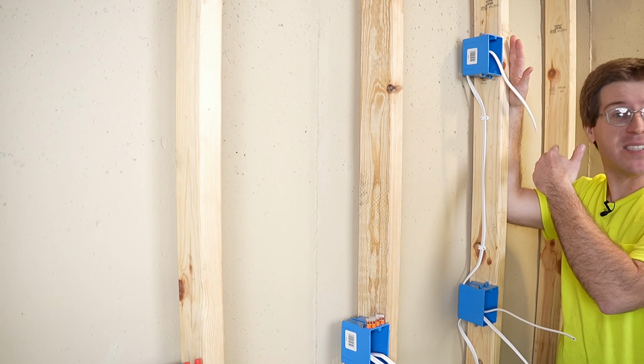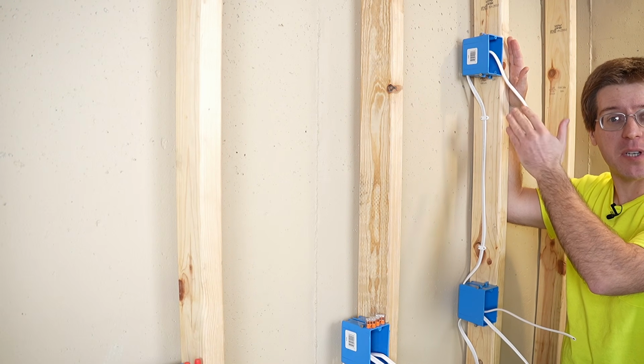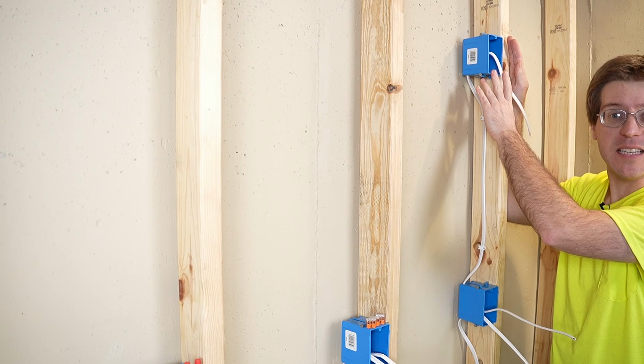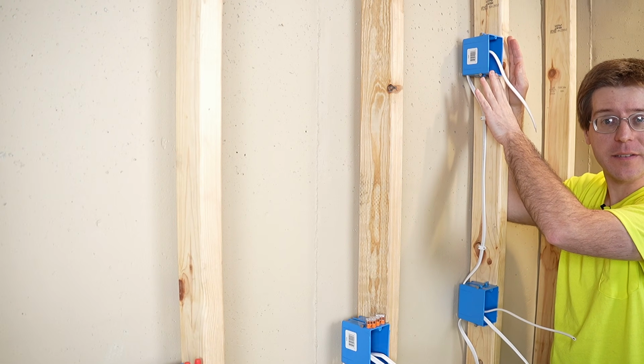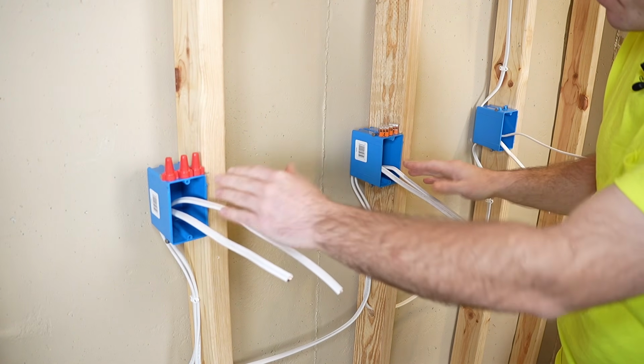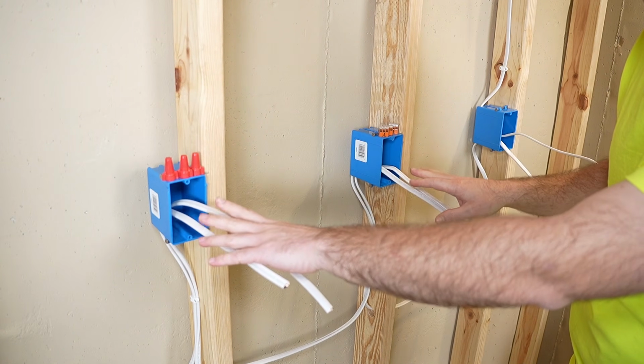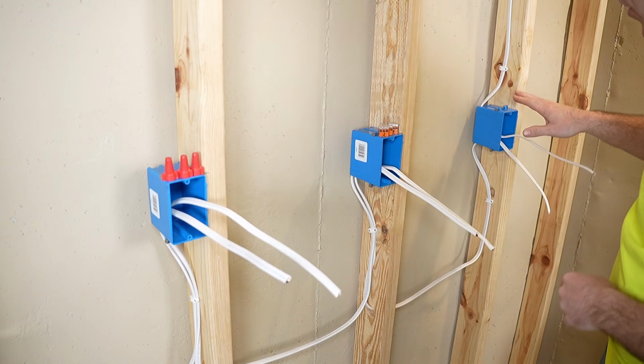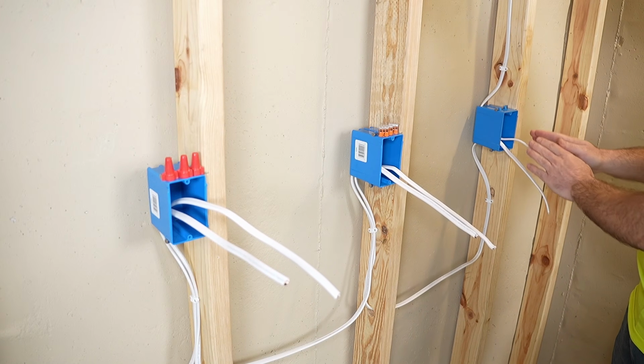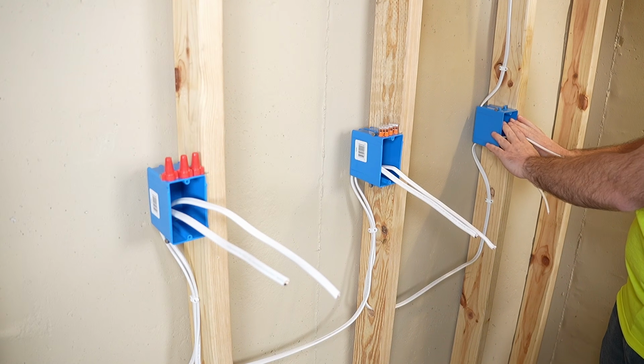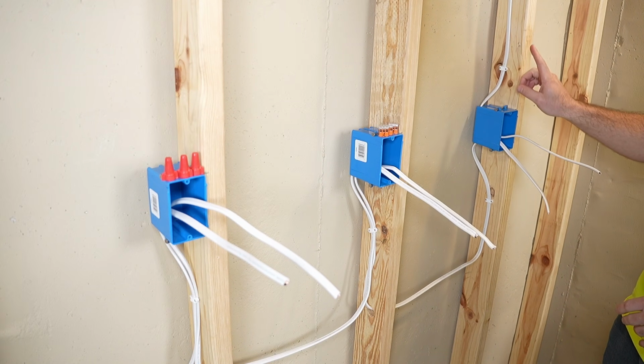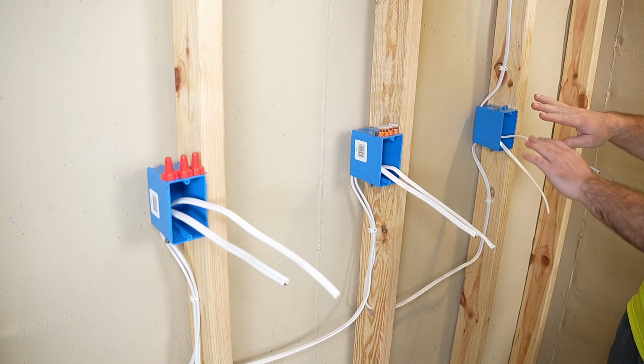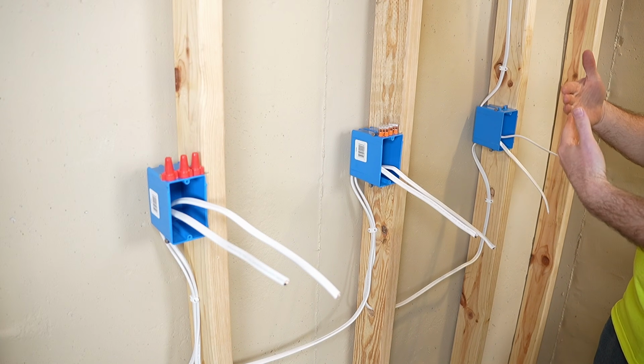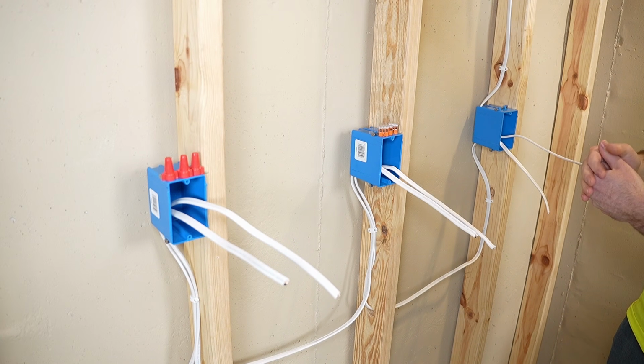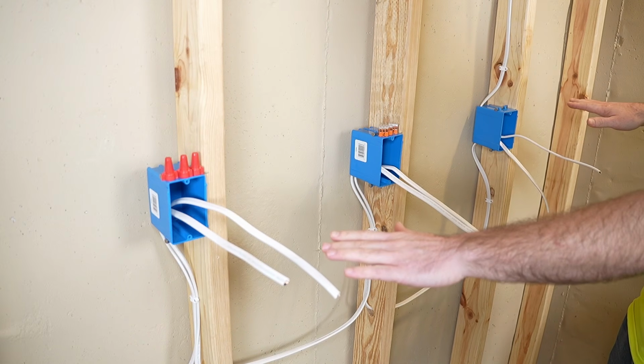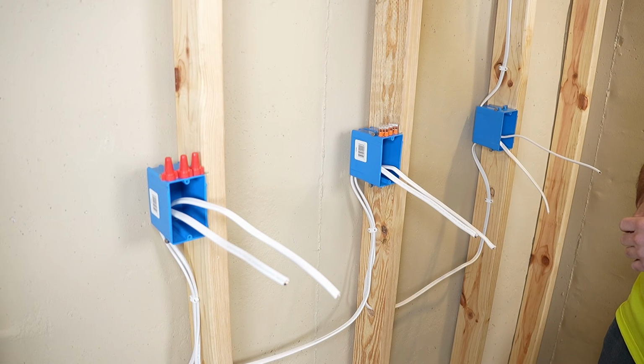And the fourth box is just gonna land directly on the receptacle, as there is no splice in this last box—this is just a dead end. So these first 2 boxes, we're actually gonna have to strip everything out and do all of our terminations right away. This third box, we're gonna get everything stripped out, and we're just gonna end up shoving the wires back in the box, and we'll do the same for that upper box as well. Then we'll be at a stopping point where we can call in for a rough-in inspection, and then we'll look at how to terminate the receptacles in these boxes.